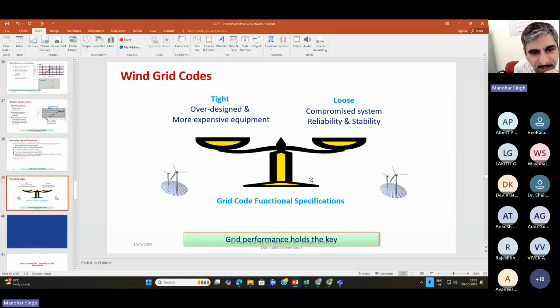Also very important, my whole game is to keep my system tight and maintain grid compliance. That means frequency should be stable and voltage should be within tolerances. For transmission, the tolerance is plus minus 5%. If I have a 400 kV station, the operator has to maintain voltage from 380 kV to 420 kV. If the voltage goes outside, he has to plan the reactor accordingly, or the other way around.